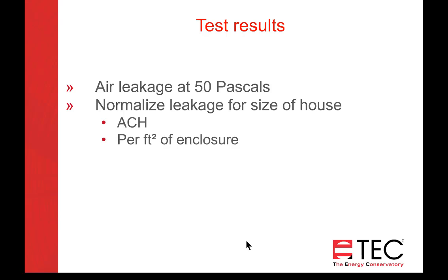If air changes per hour is the metric you're using, you'll find slab on grade, smaller homes are much harder to meet 3 air changes per hour. A better metric would be CFM per square foot of enclosure. And so far, for residential applications, only the state of New York in a multifamily unit, 7 units or larger, will allow that CFM per square foot of enclosure area as a target. And I think 0.3 was the number. CFM per square foot of enclosure area.